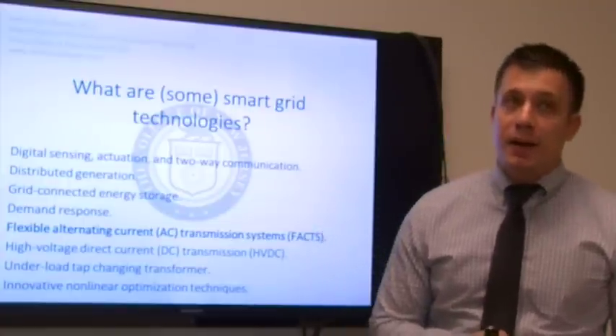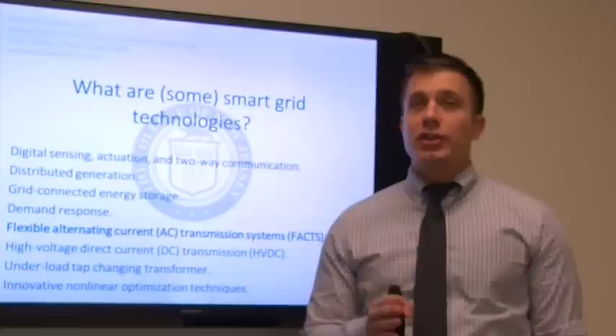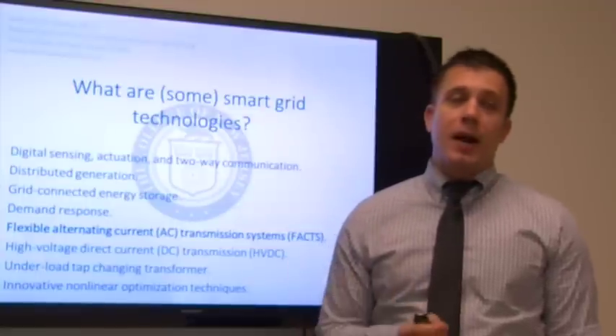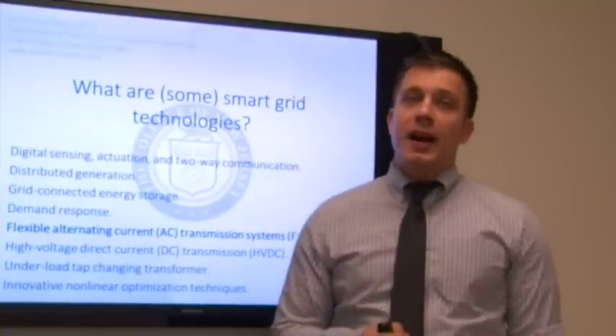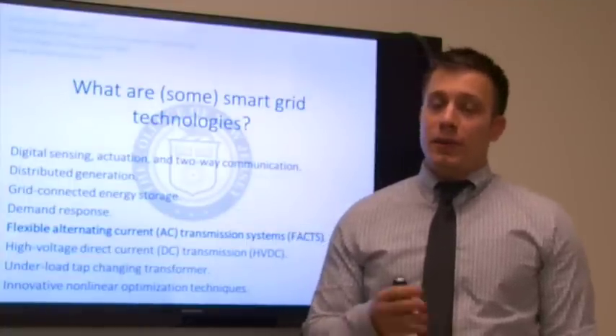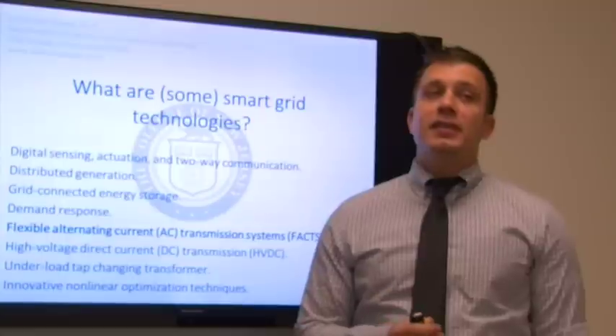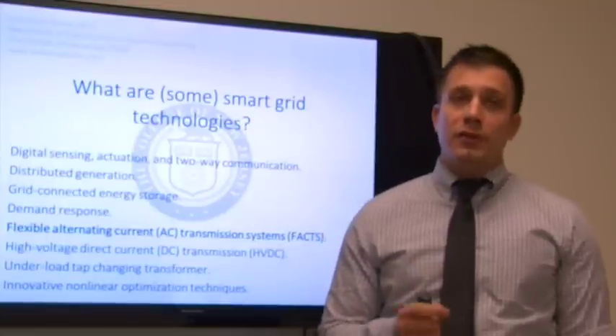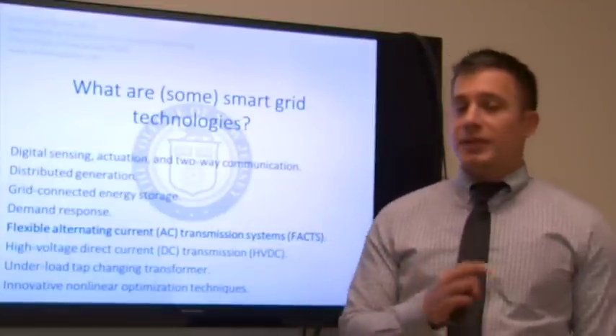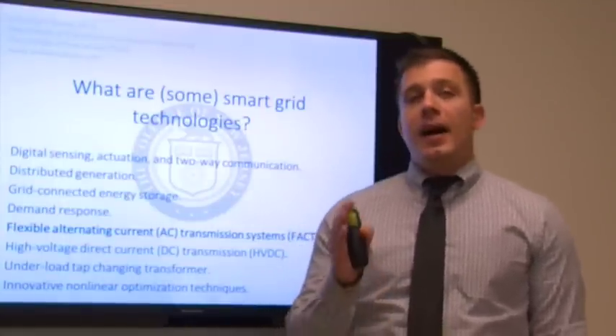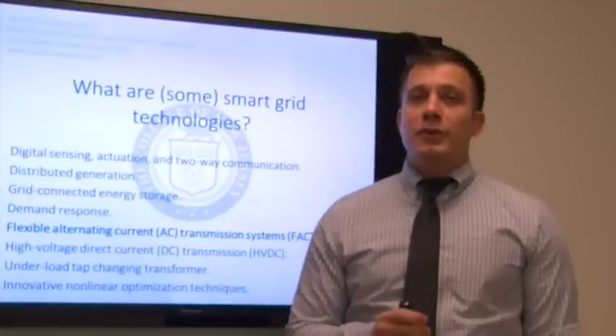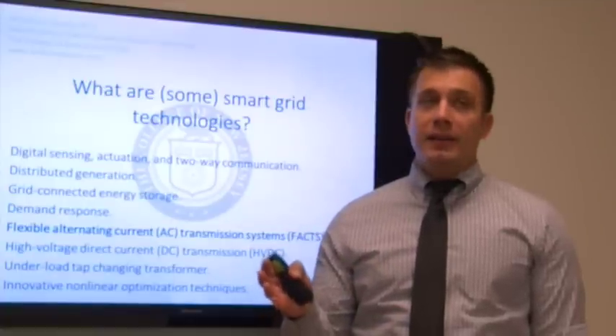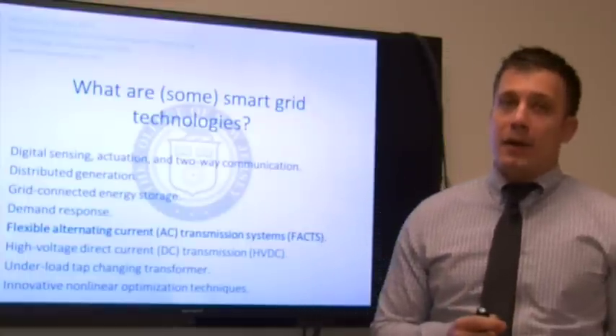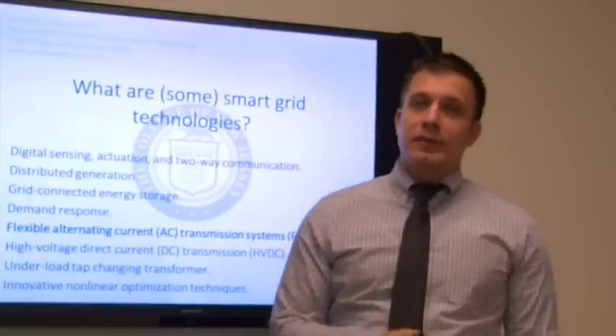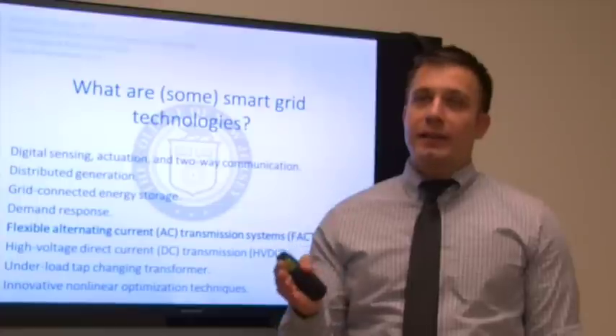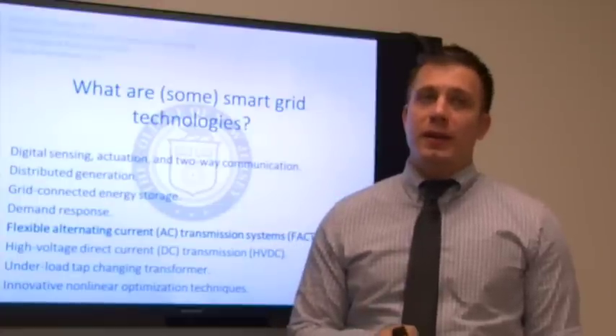Generally, it's implemented via placement of controllable voltage and current sources referred to as compensators. One popular design is the static VAR compensator, or the SVC. The SVC utilizes closed-loop control of internal thyristor switching frequencies, a lot of technical stuff there, but it uses these switching frequencies to vary its equivalent reactance and perform real-time power factor correction. For all those ECE majors out there, I'm sure you know reactance is the imaginary portion of impedance.